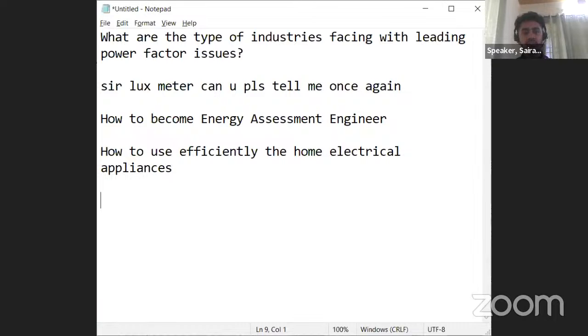A lux meter is a device that is used to measure the illuminance level of the lighting. It's a handy device that we carry with us. We have to keep it at our waist level from the ground, then measure the light illuminance level. Then we have to compare it with the chart of the standard given by the building codes or ECBC. Any standard codes we can compare, and we can give a suggestion on the amount of light, whether it is enough for this room or has to be improved.